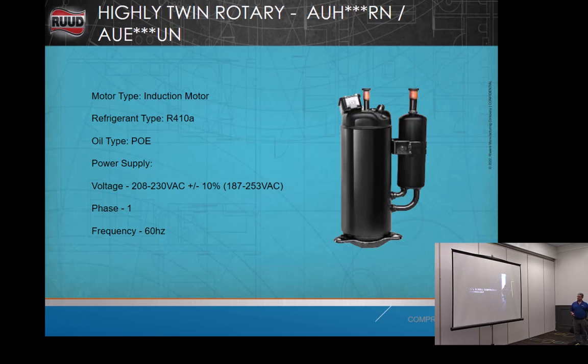So now we're looking at our Highly twin rotary compressor. POE, all steel, 208, 240, single phase. We've kind of talked and showed you some things here. We've talked about airflow and how we don't want liquid back in our compressors, and this is what happens to them, okay? But if Copeland and LG don't like liquid, Highly has stepped up and put an accumulator on the side of their rotary compressor and says we really don't like liquid, okay?